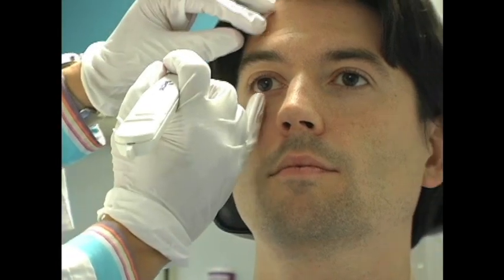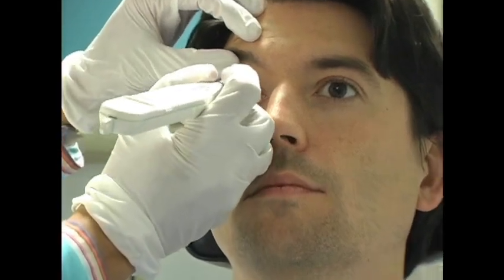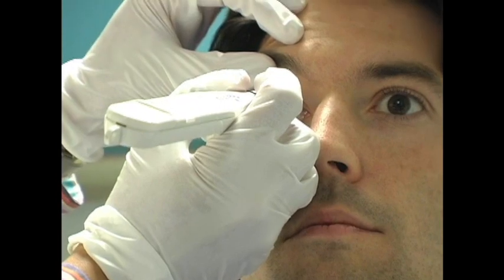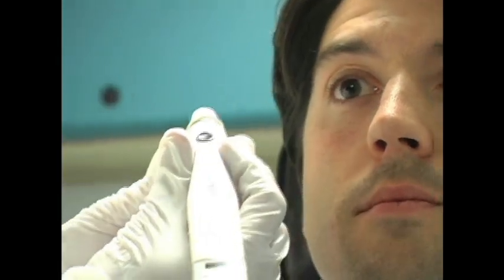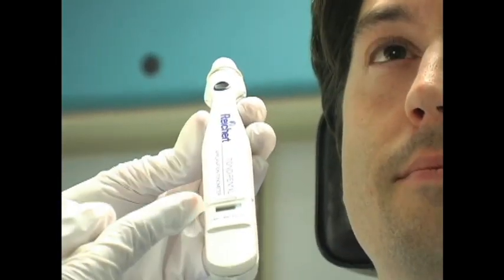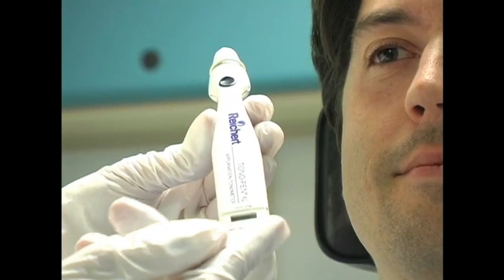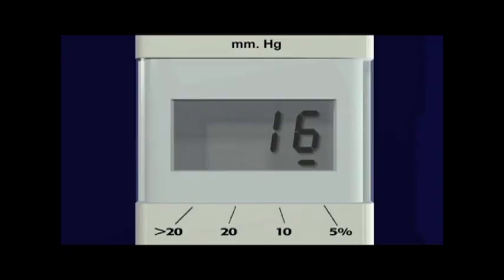Have the patient focus with the non-tested eye on a distant object, such as a visual acuity chart, a doorknob, or a light switch. Next, lightly tap the center of the cornea several times. You will hear clicking while you are tapping. Continue tapping until you hear a beep, then record the pressure from the LCD screen. Also note the error of the reading by identifying the location of the small hash mark in relation to the error scale located next to the screen. Optimal measurement requires an error reading of 5%.